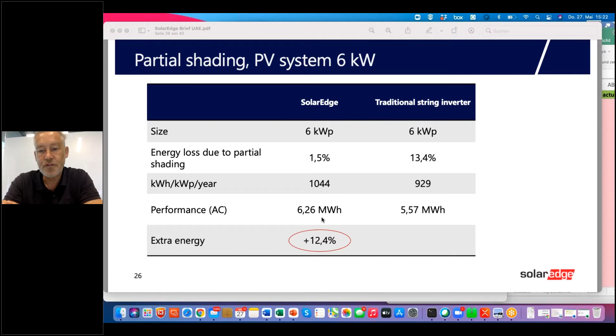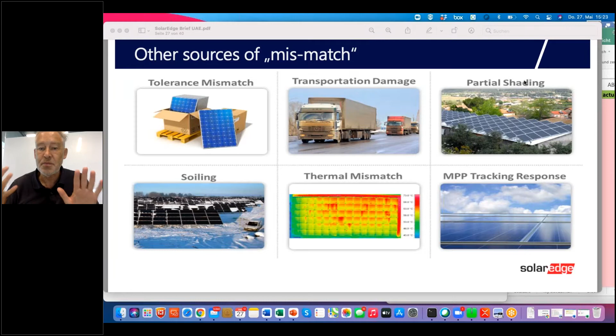But the question always comes up: is this everything? Is it only when I have shading in a system where this extra power optimizer has value? The clear answer is no. Whenever there is a mismatch - meaning one panel performs differently than the others - that's called mismatch, and I want to explain where mismatch can happen.